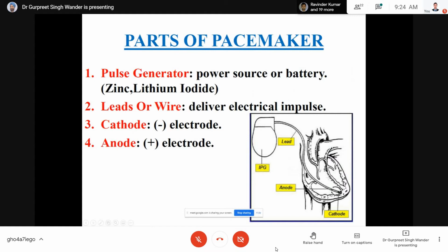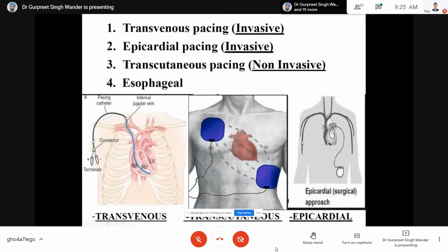And as I said, these 1, 2, or 3 leads are put, which have an anode and a cathode at the tip. This lead is insulated, it is very soft, and it has to be insulated so that it doesn't discharge on the way. And the electrical circuit is, now this is a bipolar pacemaker in which the negative and the positive are next to each other. Sometimes we use the cathode here and the anode is the pacemaker itself. Then the pulse generator stimulus artifact is actually bigger.